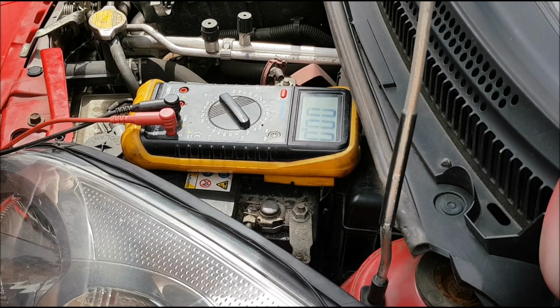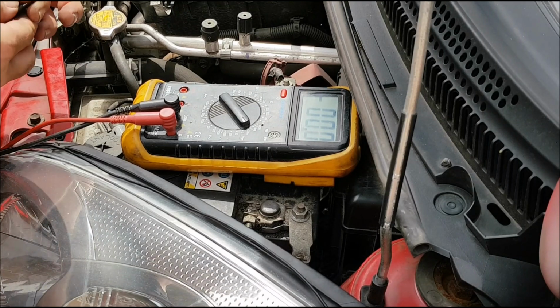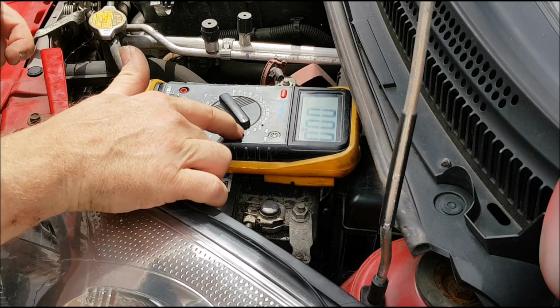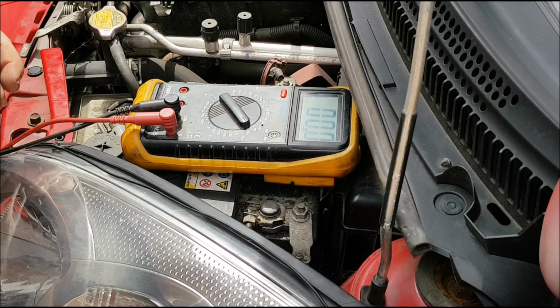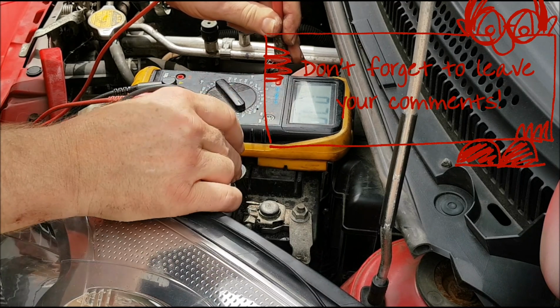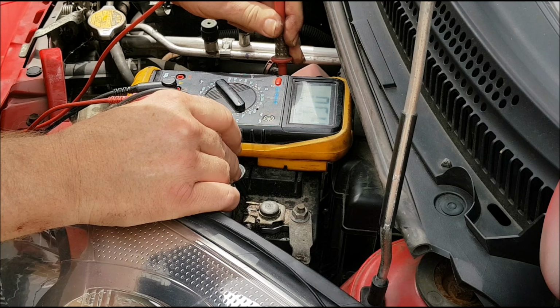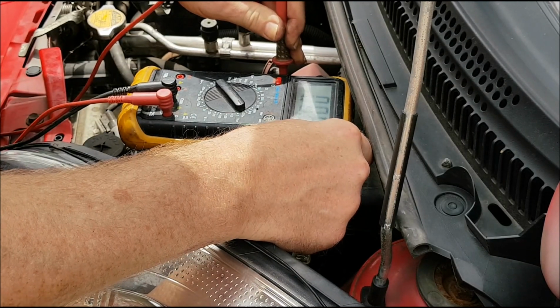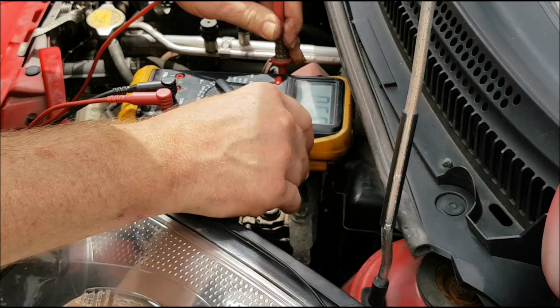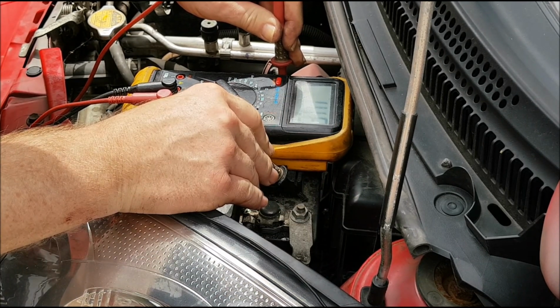Here I've got my digital multimeter sat on top of the battery, set on millivolts DC. I measure the voltage between the positive terminal and the dirt on the top of the casing just next to the negative terminal, and I'm getting around 6 to 7 millivolts. I measure in a variety of places - 6 millivolts there, with my probe directly onto the plastic.